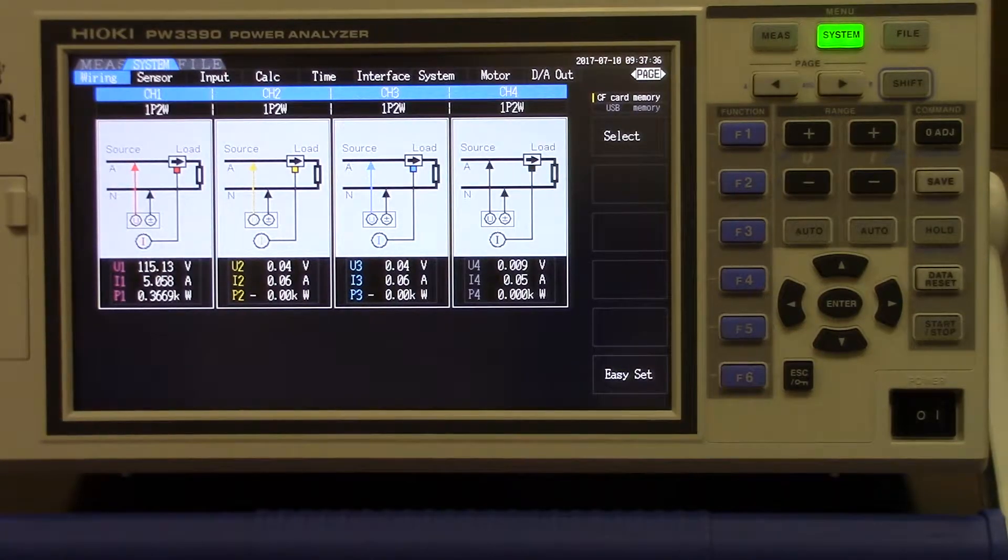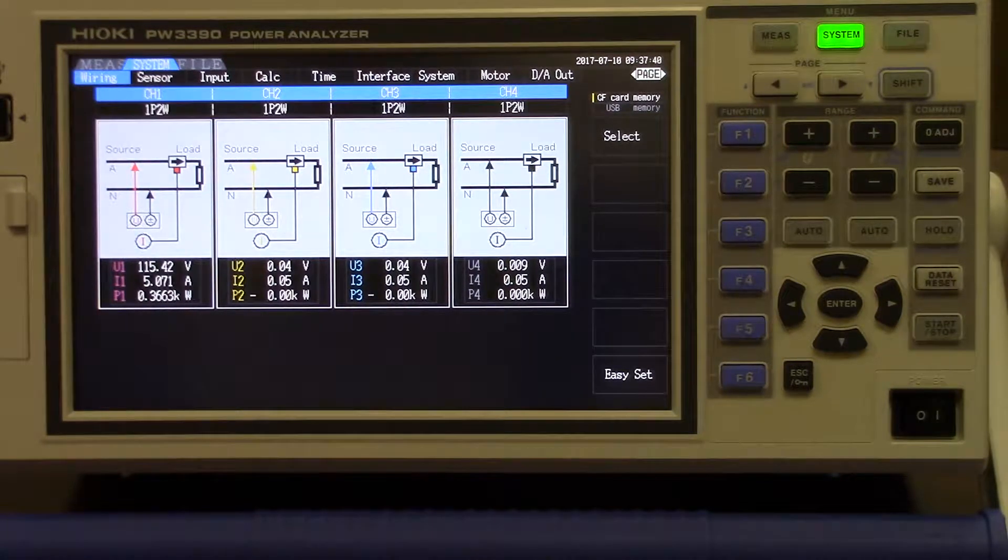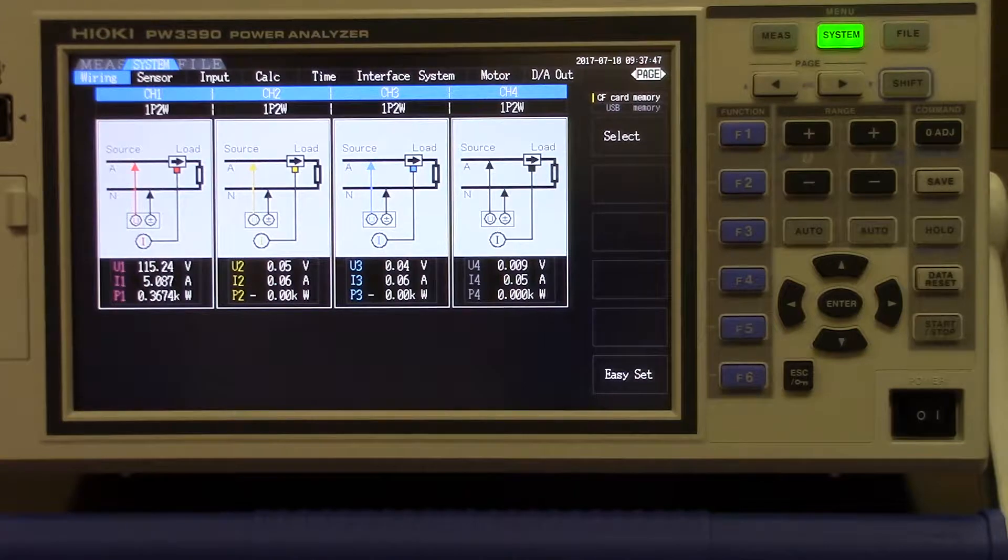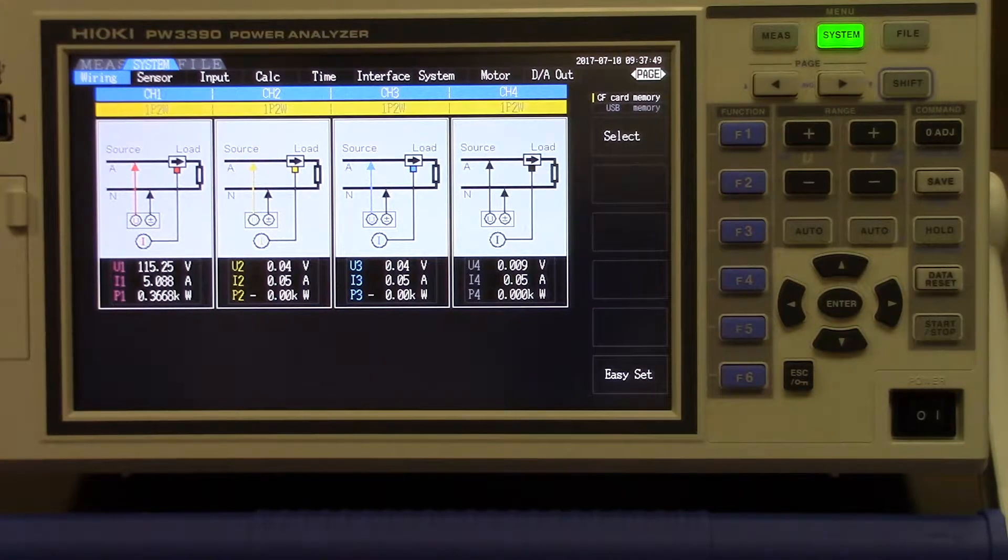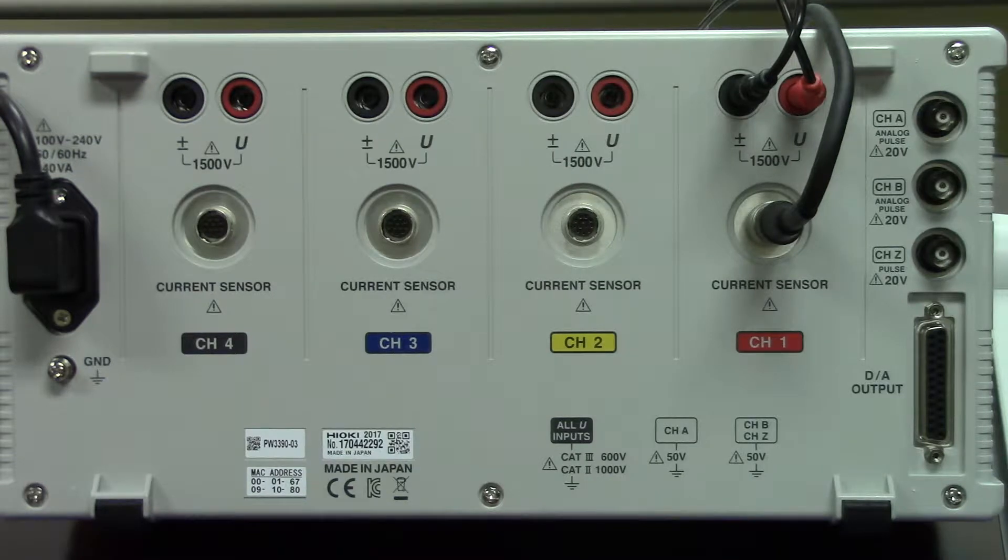This is the Hioki PW3390 power analyzer, which is a single phase 2-wire to 3-phase 4-wire 4-channel power analyzer that can be used to measure systems and inverters operating from DC up to 200 kHz. Voltage measurements can go as high as 1500 volts AC and DC and currents from 20 amps up to 1000 amps depending on the clamp used.